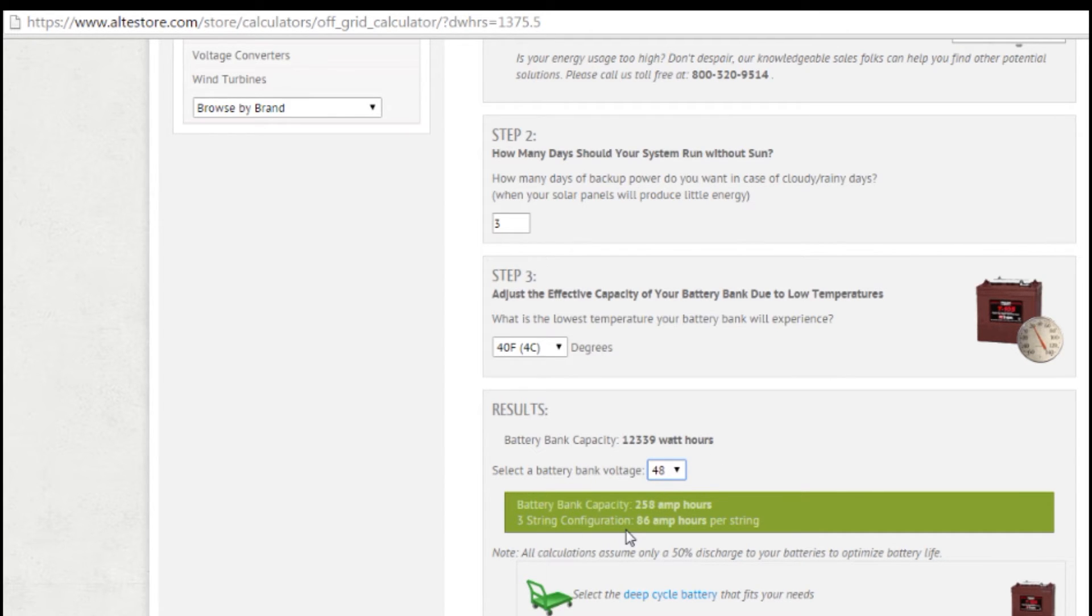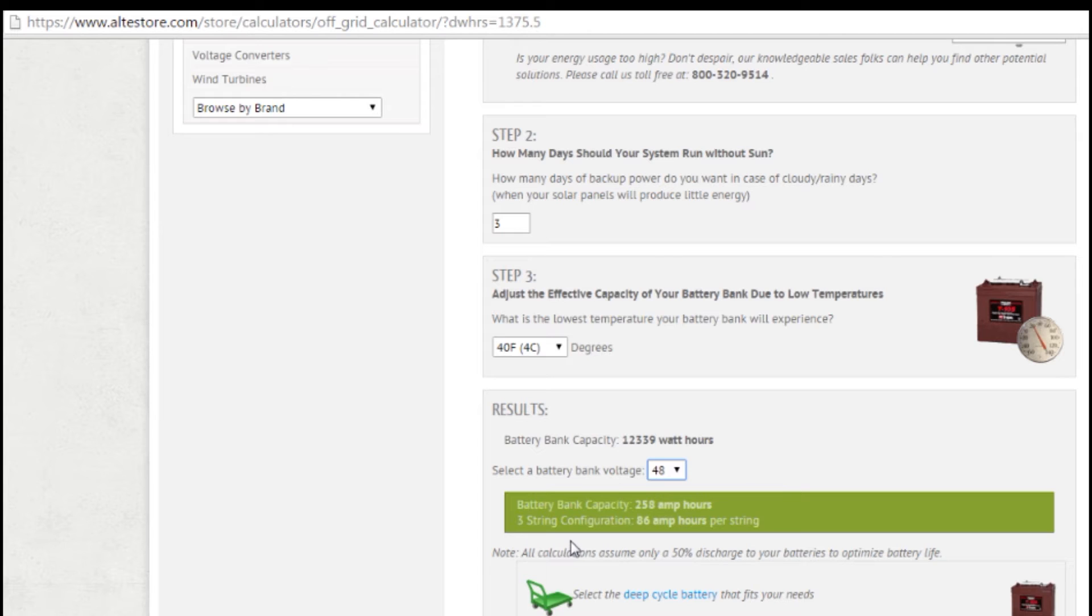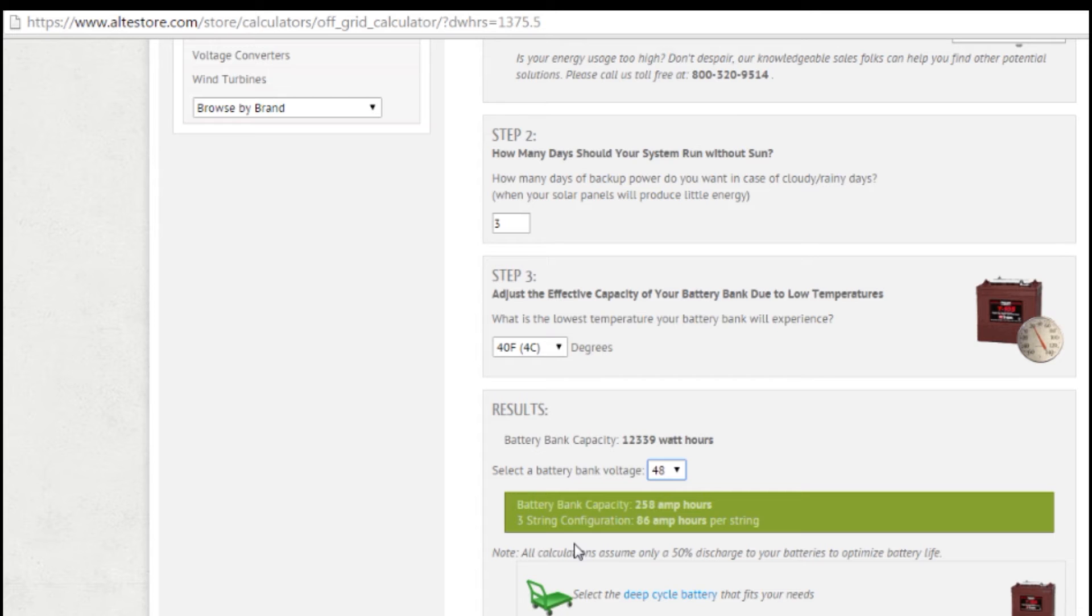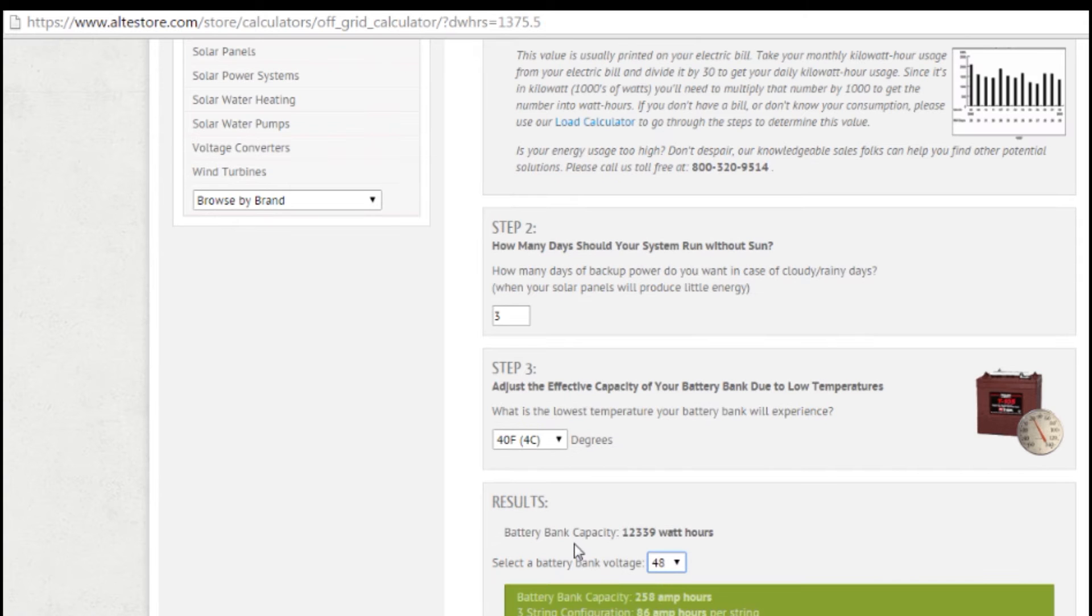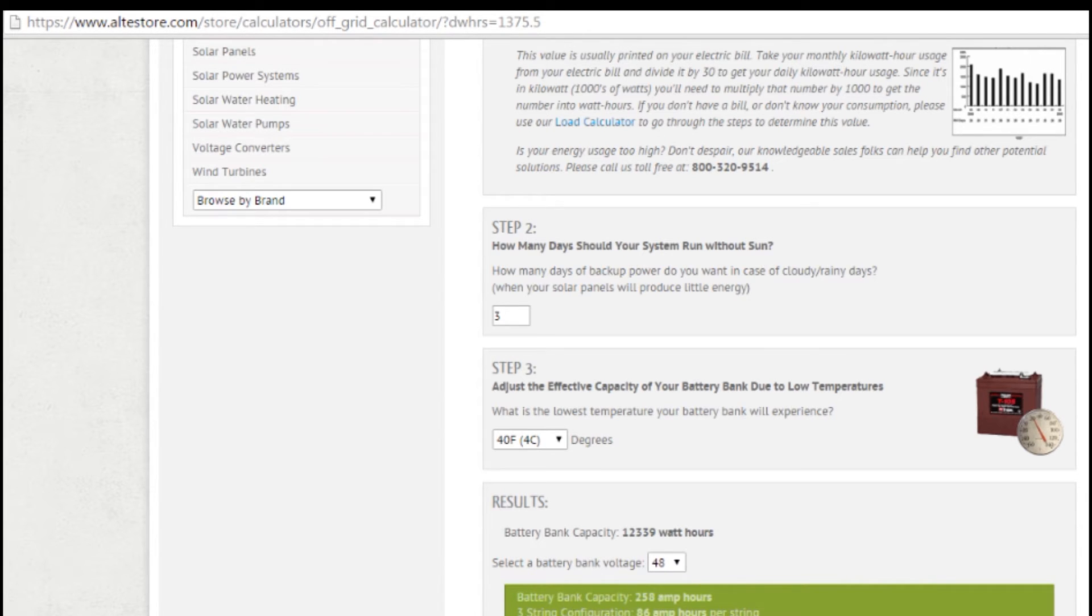Now you'll see the next line says three-string configuration. If you are wiring multiple parallel strings of batteries, this tells you how many amp hours each string would need to be. Now you don't ever want to go more than three strings in parallel, and that might actually even be pushing it a little bit. You want to keep your number of parallel strings to a minimum, because when you wire batteries in parallel, they're going to run the risk of charging and discharging unevenly. So you want to make sure that you've got the fewest number of parallel strings. So a lot of people will actually try and just keep at one string. So if you've got a 48 volt battery bank, you can stay at 258 amp hour string.